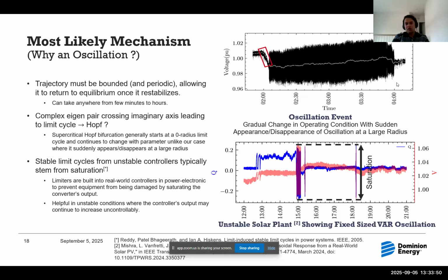Something much more common is scenarios where real world controllers become unstable, which we've seen at multiple solar plants: limit cycles born out of unstable controllers coupled with hard limiters. We've seen it in many solar cases where you take an outage in the system and the volt-var control or the AVR becomes unstable at some solar plant, and then it starts bouncing between the limits set on the controller. This is a far more common case in these local instabilities, or local controllers being unstable, and hard limiters are everywhere in real world controllers.